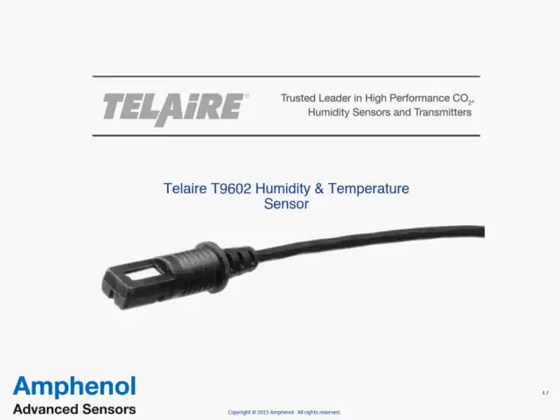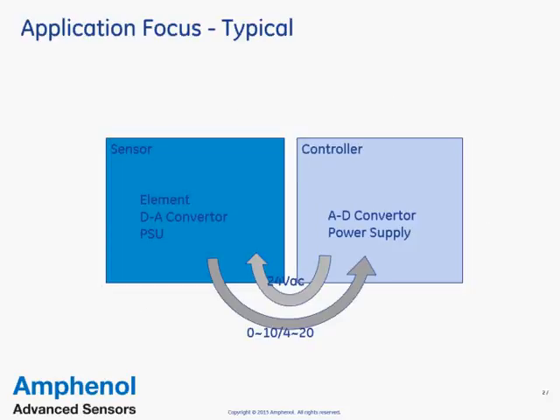We'll start by looking at a historical way of putting a humidity sensor into a control system, where typically we'd have a sensor transmitter and a controller. The controller has a power supply on board, providing 24-volt AC to the sensor, which has its own onboard power supply unit. From its element it uses either a digital to analog converter or some form of amplifier to send a 0 to 10 or 4 to 20 milliamp signal back to the controller. Within the controller, that analog signal is often converted again to digital so the controller can microprocess the information and pass it along to some form of energy management system.